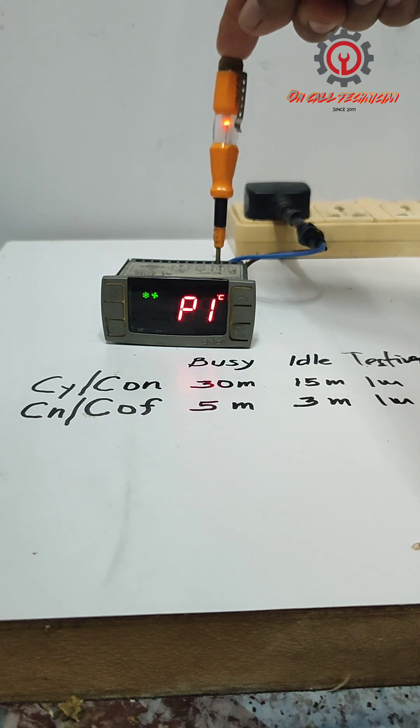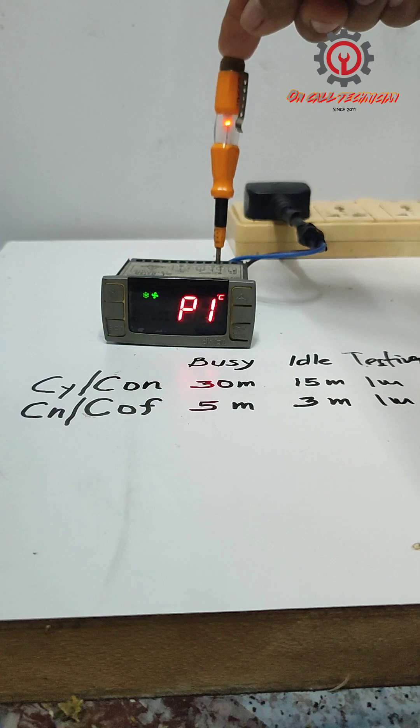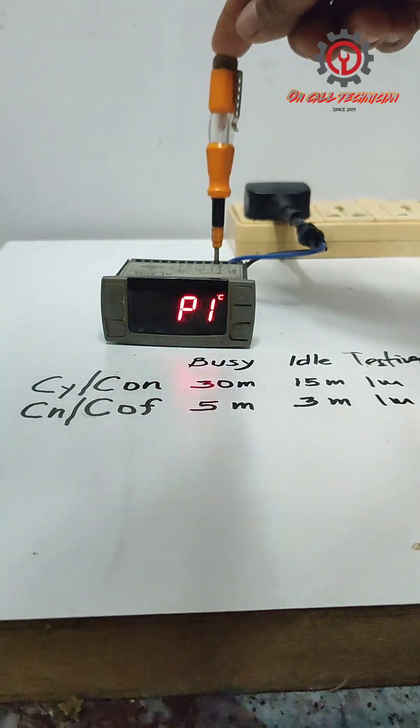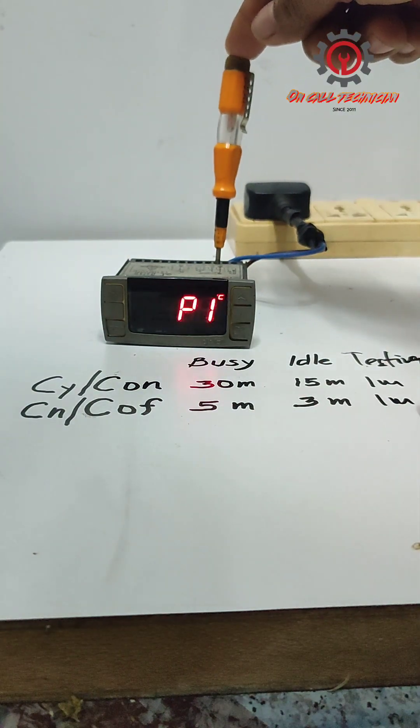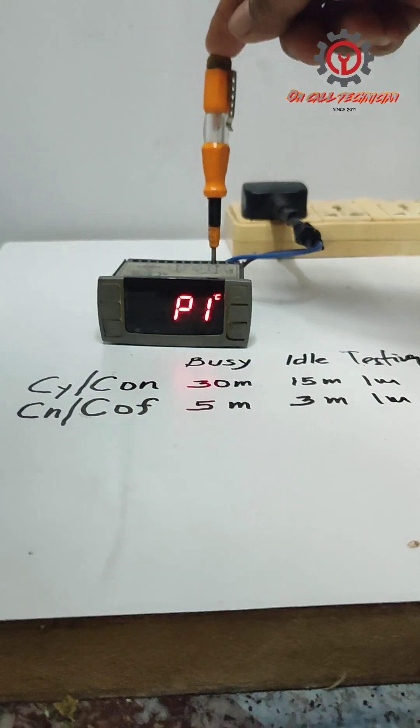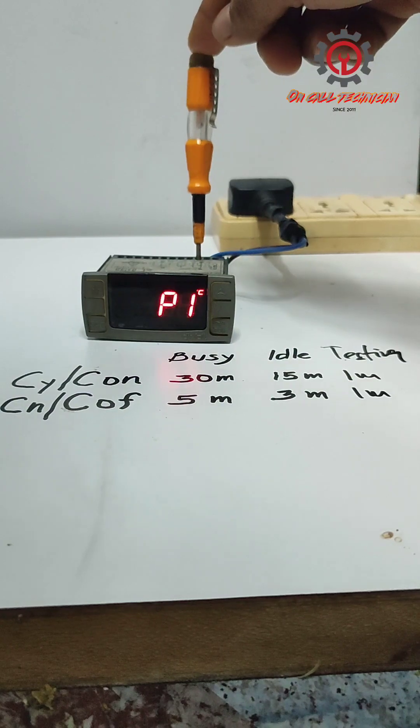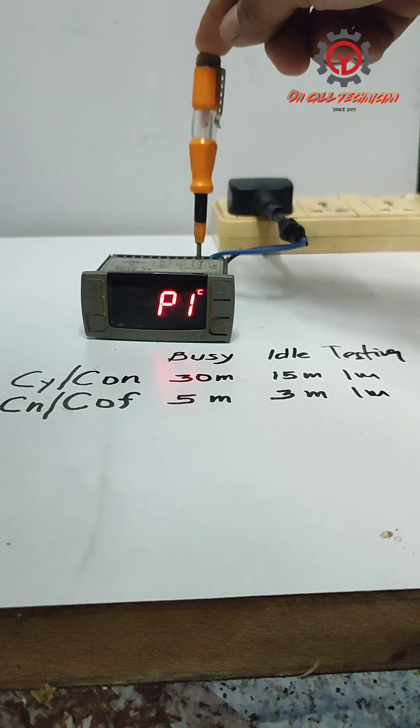My test pen is on terminal number three proving the compressor is engaging. See, cut off after one minute count. Count one minute again and the compressor and fan motor will engage again.